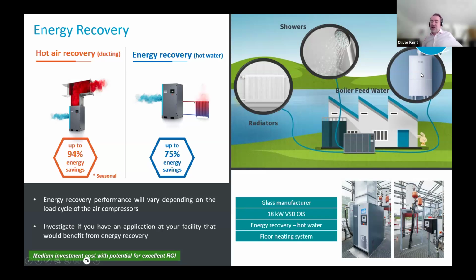Probably the most common usage for energy recovery systems is to use the heat in the pre-feed of your boiler water. If you are using hot water or steam in your industrial process, you could use the energy from your compressed air system to preheat the boiler feed water. Even if you can preheat by 10, 15 degrees C, that's going to save you a lot of energy in the long run.